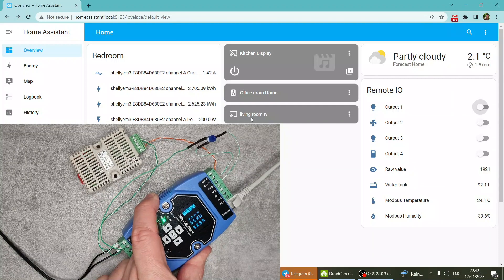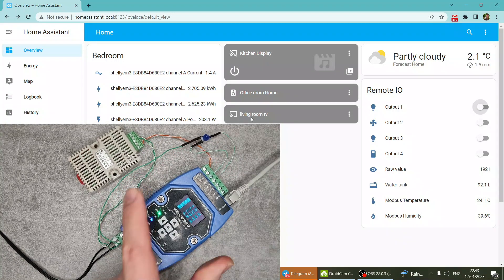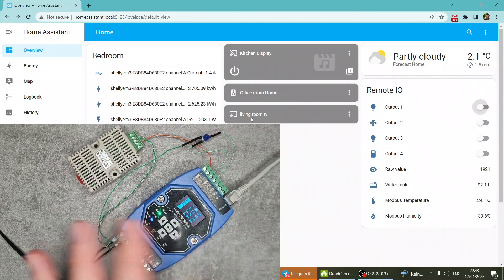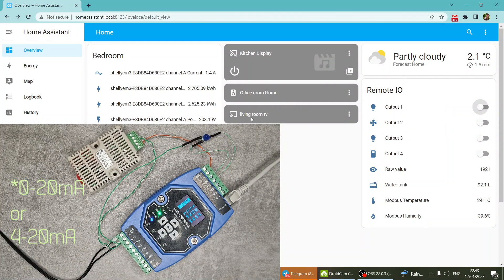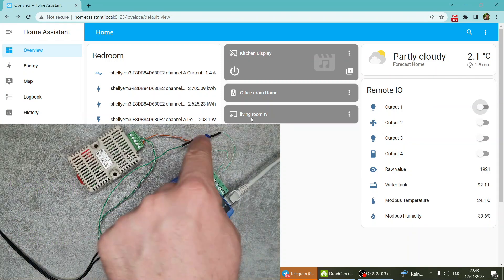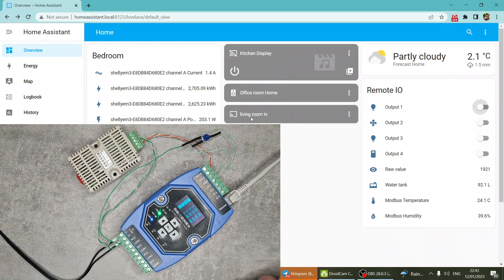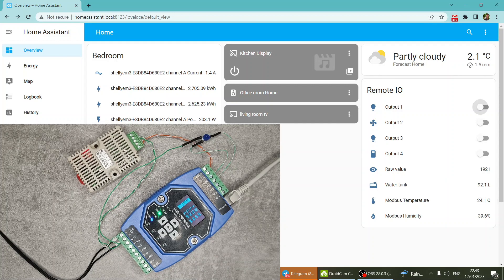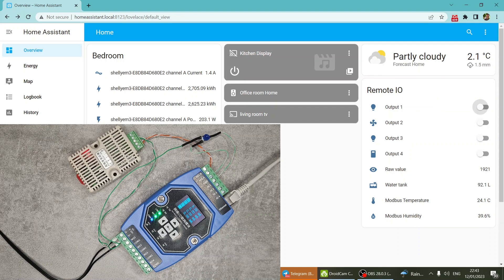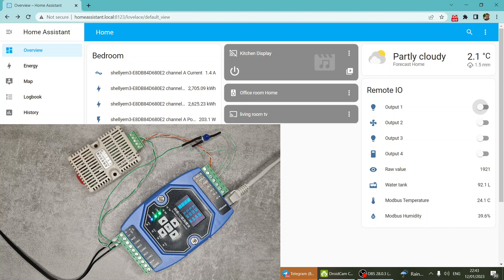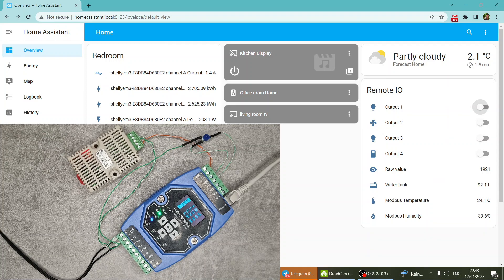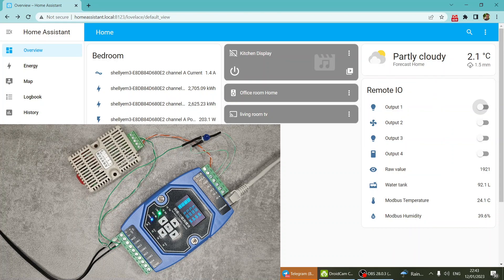So AI1, AI2, 3, and 4. And this supports current inputs, 0 to 20 milliamps, 4 to 20 milliamps. And I've just connected a potentiometer just for testing. And what I have done is I created two values. There is a raw value which comes from the input or from the register, and I've created a template which uses a calculation to calculate it into a human readable value.